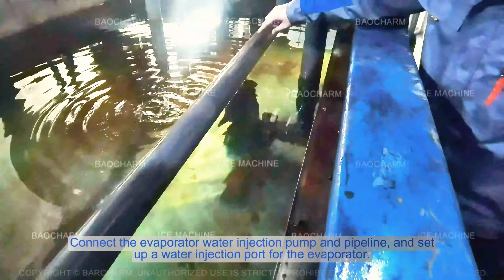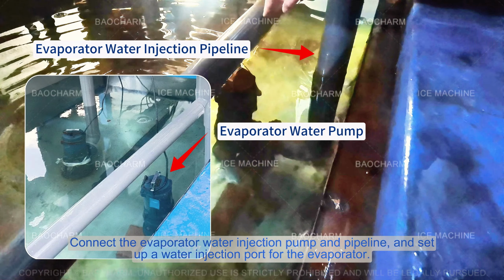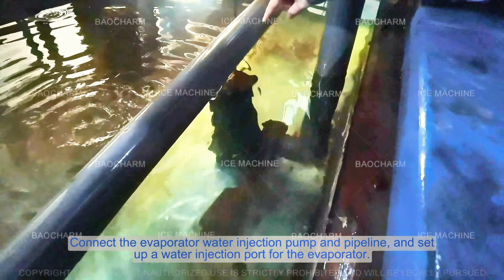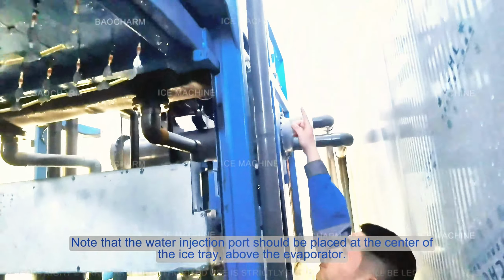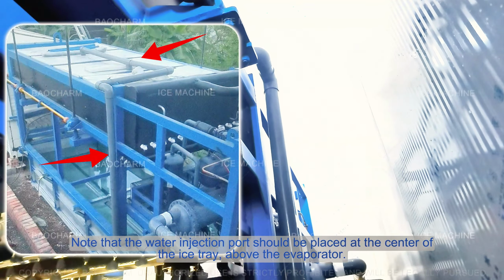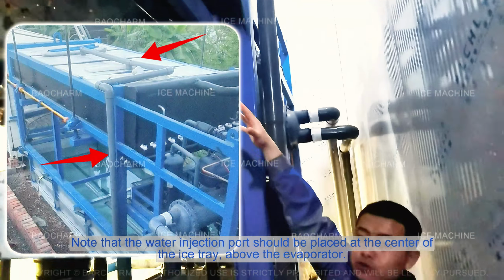Connect the evaporator water injection pump and pipeline, and set up a water injection port for the evaporator. Note that the water injection port should be placed at the center of the ice tray, above the evaporator. Install an external liquid level sight tube on the evaporator to monitor the water level inside the evaporator later.